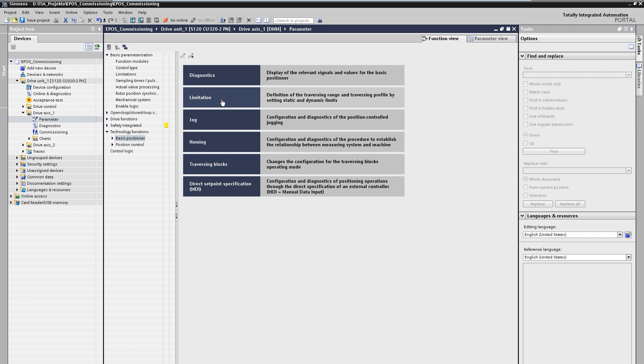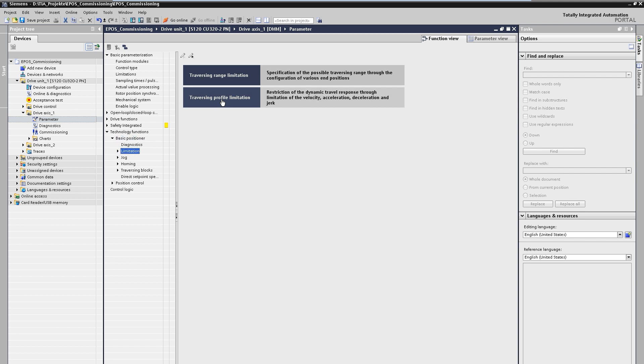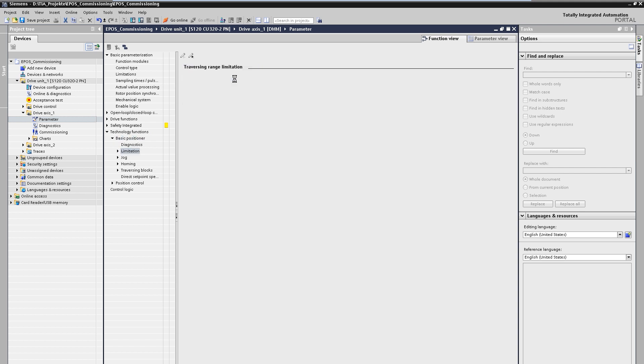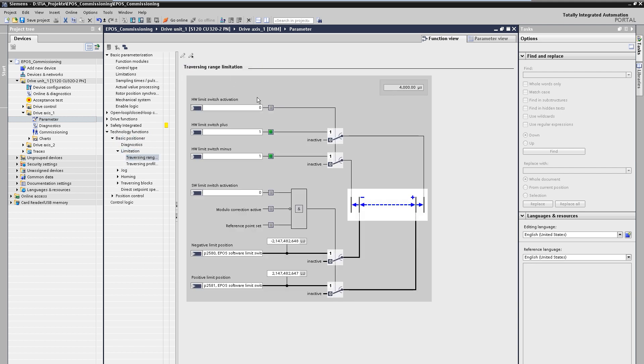Under limitations we can first limit the travel range by hardware and software limit switches. The hardware and software limit switches prevent the mechanical limit stop of linear axes from being exceeded and would have to be activated explicitly if required.